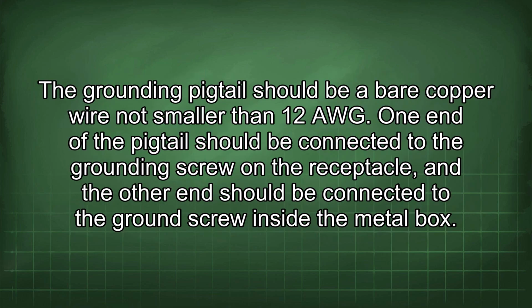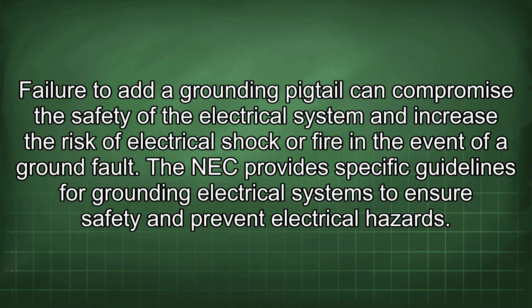The grounding pigtail should be a bare copper wire not smaller than 12 AWG. One end of the pigtail should be connected to the grounding screw in the receptacle, and the other end should be connected to the ground screw inside the metal box. Failure to add a grounding pigtail can compromise the safety of the electrical system and increase the risk of electrical shock or fire in the event of a ground fault.